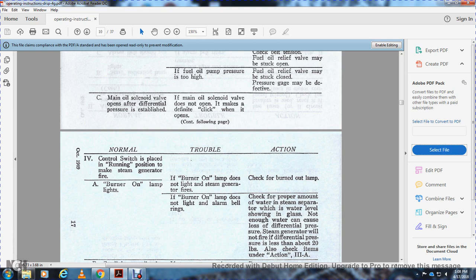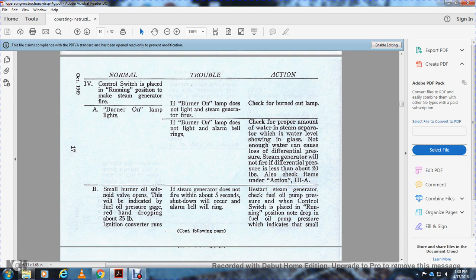Check for the proper amount of water in the steam separator with the water level showing in the glass. Not enough water can cause loss of differential pressure. Steam generator will not fire. The differential pressure is less than 20 pounds. Also, check the items under the action of 3A.